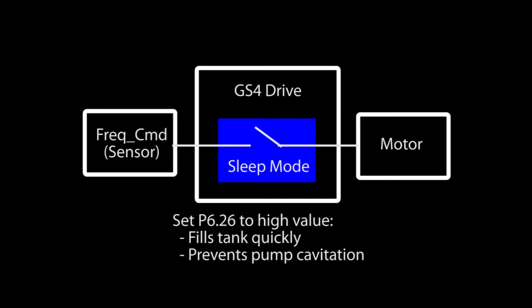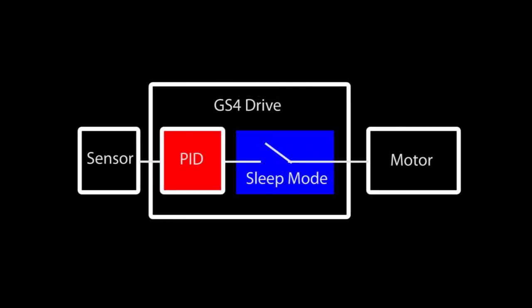Is there a way to do this without tricking the drive's min frequency? Well, yeah, there is. You just tell the drive to use PID as the frequency reference. PID's job is to get a process to whatever level you specify as quickly and efficiently as possible, right? Well, that's exactly what we want. We show you how to use PID to do this in the other videos in this series.